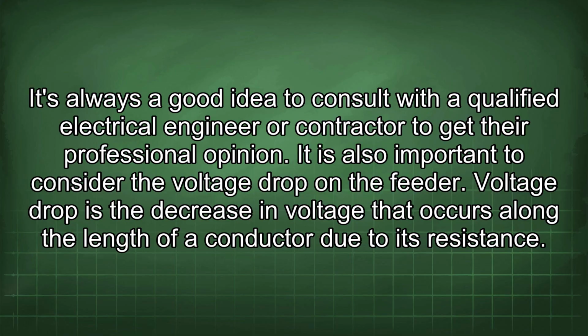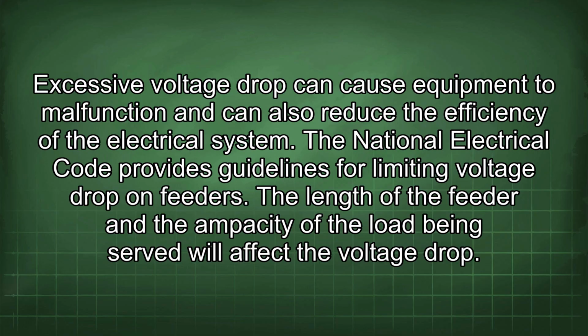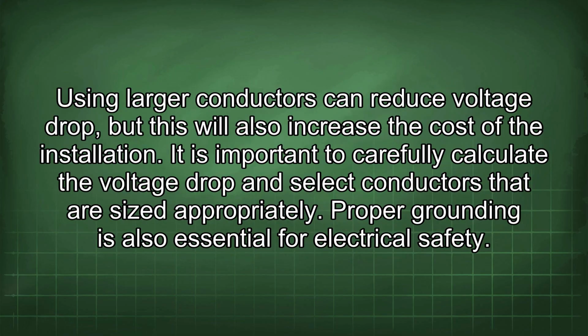It is also important to consider the voltage drop on the feeder. Voltage drop is the decrease in voltage that occurs along the length of a conductor due to its resistance. Excessive voltage drop can cause equipment to malfunction and can also reduce the efficiency of the electrical system. The National Electrical Code provides guidelines for limiting voltage drop on feeders. The length of the feeder and the ampacity of the load being served will affect the voltage drop. Using larger conductors can reduce voltage drop, but this will also increase the cost of the installation. It is important to carefully calculate the voltage drop and select conductors that are sized appropriately.